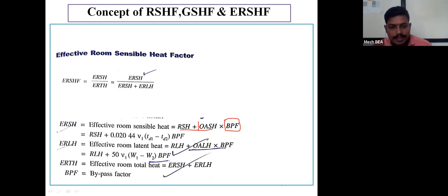Whereas outside air sensible heat is given by the equation 0.02044 V1 (TD1 minus TD2) into bypass factor. And effective room latent heat is room latent heat plus outside air latent heat. So here, that outside air latent heat I have to multiply by the bypass factor. Outside air latent heat is given by the equation 50 V1 (small w1 minus small w2) into bypass factor. And effective room total heat is given by effective room sensible heat plus effective room latent heat.